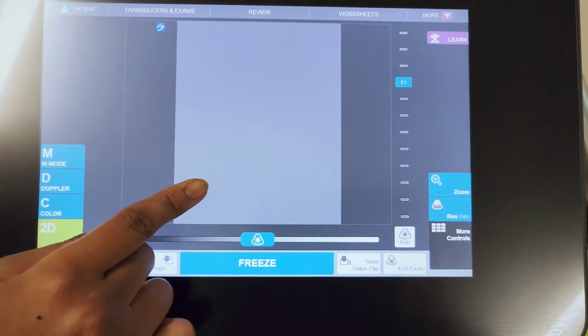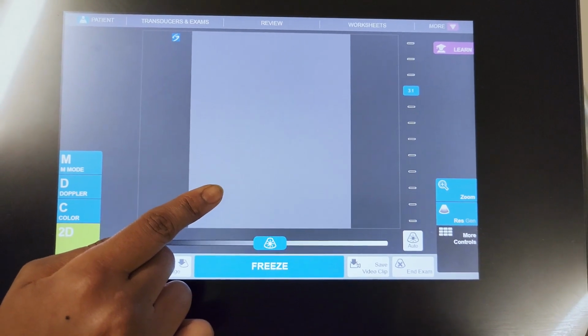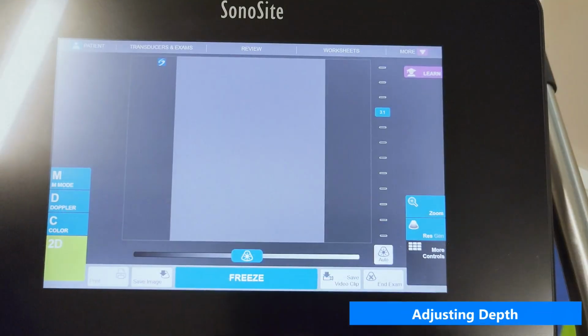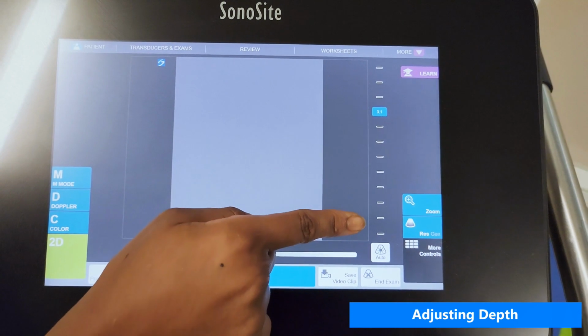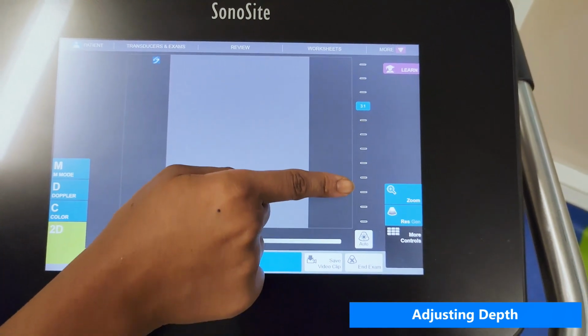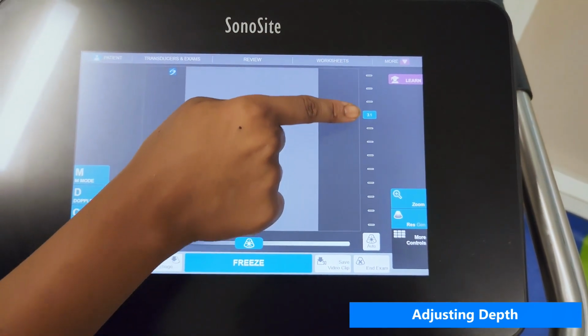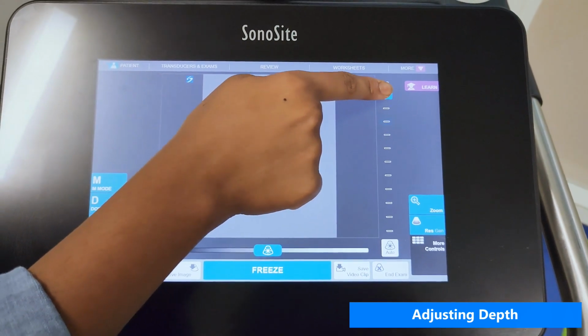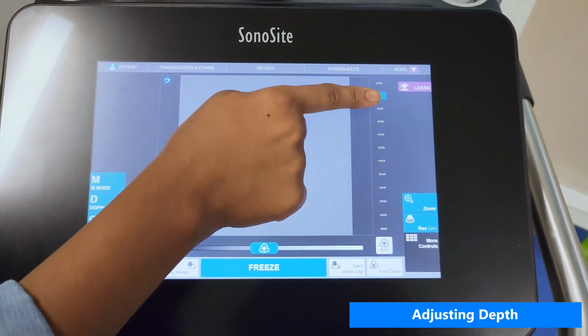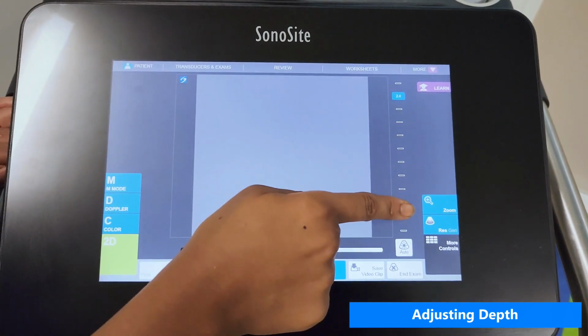To optimize your scan, you have to adjust depth and gain. First, to adjust depth, you can move the blue scroll marker on the scroll bar on the right side of the touch screen for adjustment of imaging depth. Moving up decreases imaging depth, and moving down increases imaging depth.